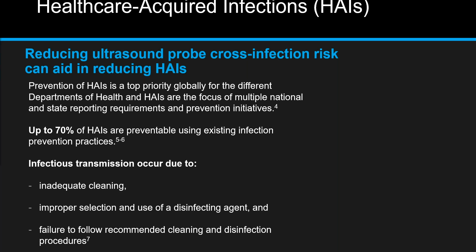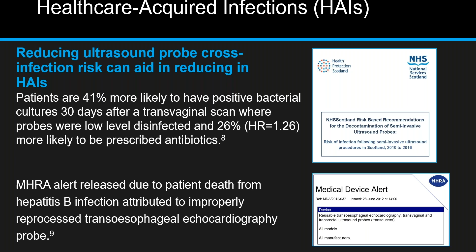So, reducing ultrasound probe contamination, again, can result in reducing HAIs. Patients are 41% more likely to have a positive bacterial culture 30 days after a transvaginal scan where the probe was low-level disinfected, and 26% more likely to be prescribed antibiotics, both suggesting, in fact, that the low-level disinfection led to infection, which led to antibiotics. An MHRA alert was released due to a patient death from hepatitis B infection due to improperly reprocessed transesophageal echocardiography probes. So here's an example of failure of proper cleaning and disinfection leading to a serious infection.